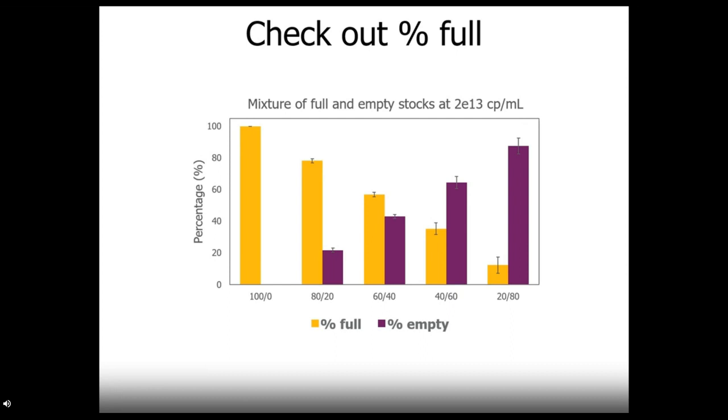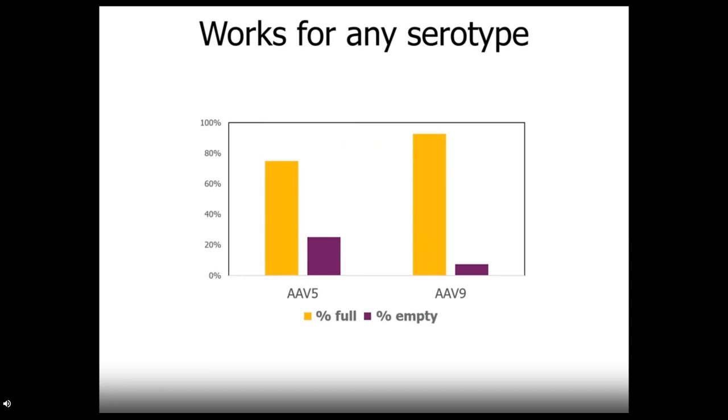To look more into our ability to see percent full values, we took stocks of empty and full AAV9 and mixed them at different ratios. For each combination, 100% full stock, 80% full stock, and so on, Stunner gets a good read on the data and percent full and percent empty align well with our expected values. And this application works for any serotype. Just tell Stunner the basics about what serotype you have and what its DNA payload is, and Stunner takes care of the rest of the heavy calculating.